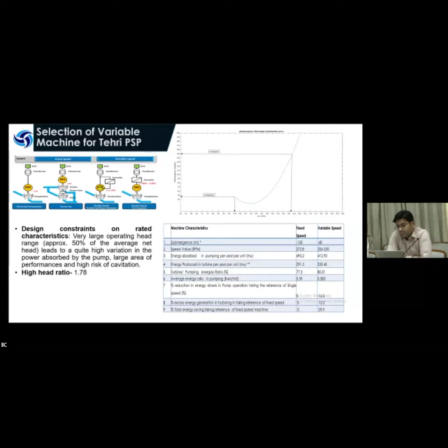This is the schematic diagram of the TEHRI PSP. It shows the asynchronous machine connected to the reversible turbine with the shaft, the rotor circuit breaker and generator circuit breaker, the direction reversal switch used for changing the direction, forward or reverse, based on the selection of pump or generating mode, and the main transformer and unit circuit breaker at 400 kV.